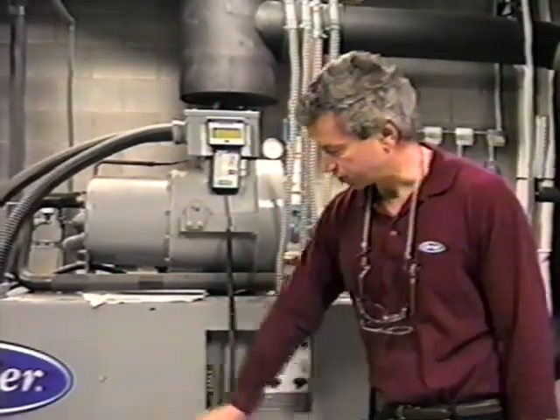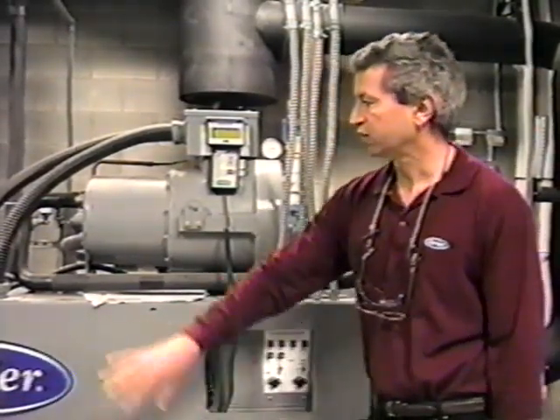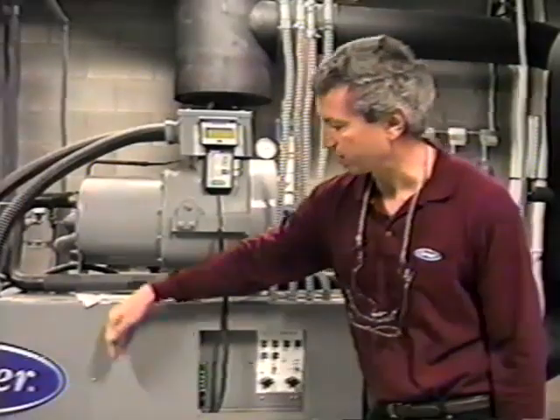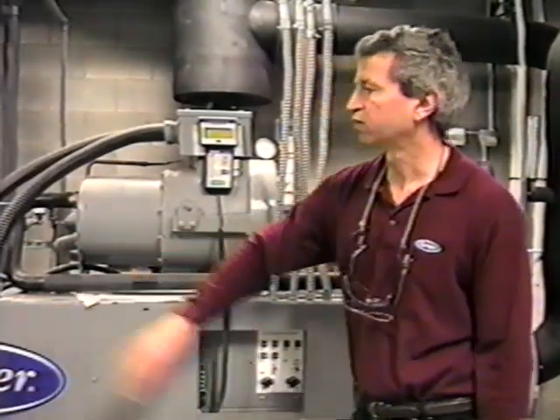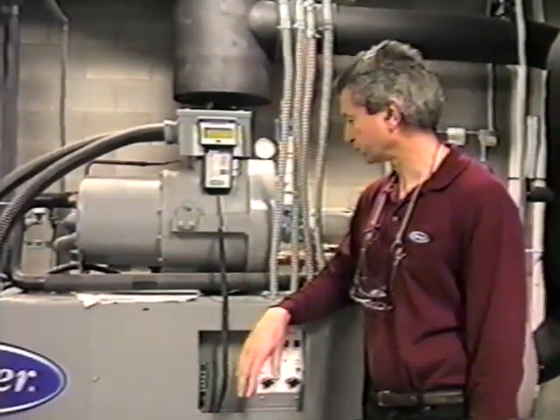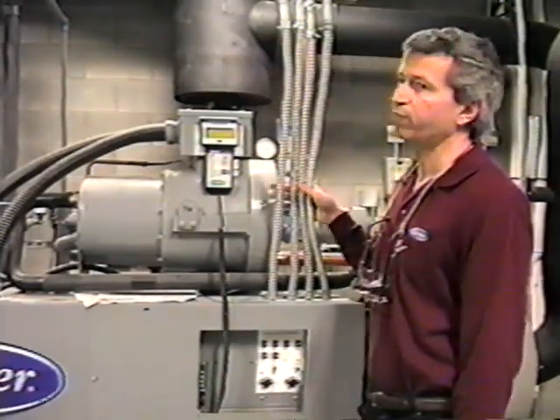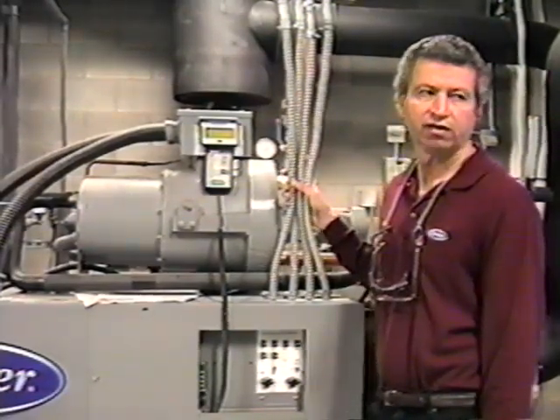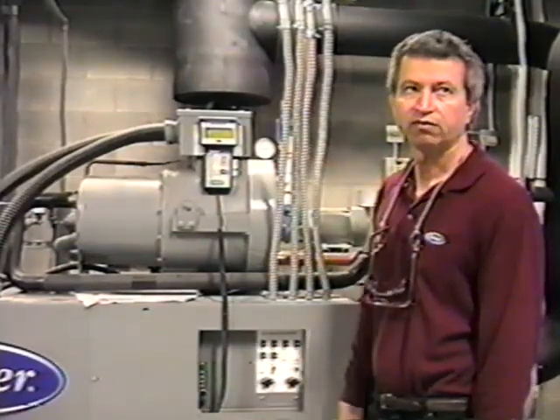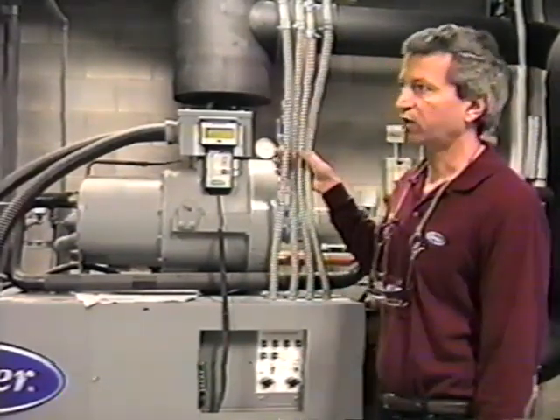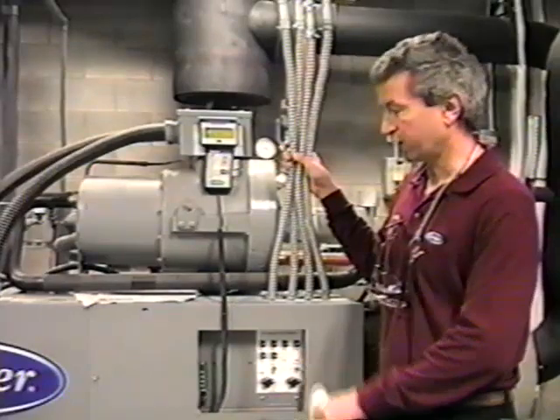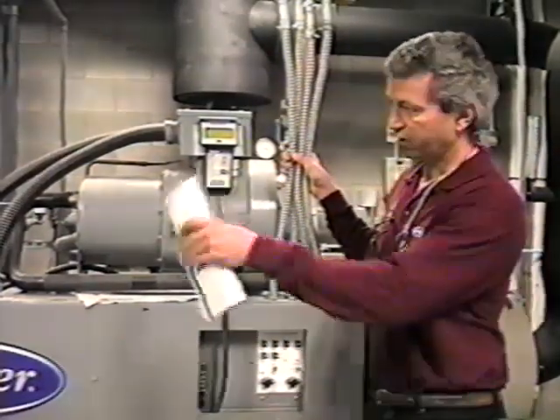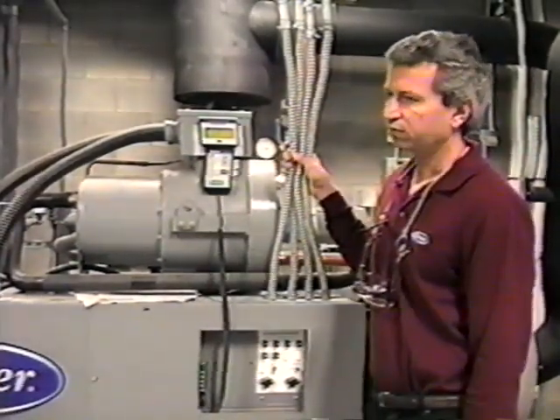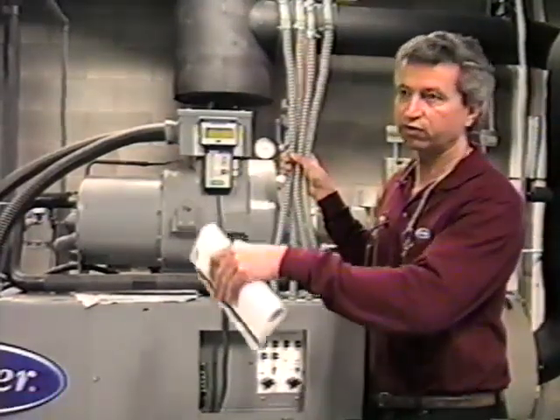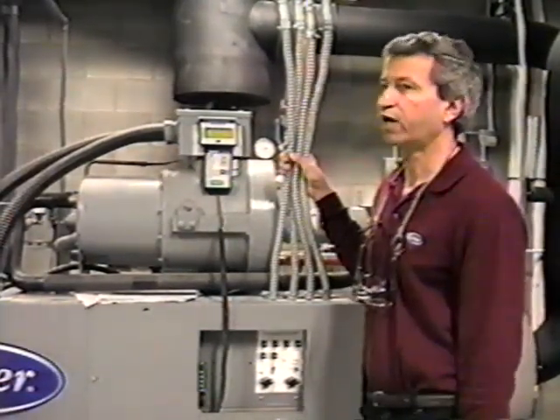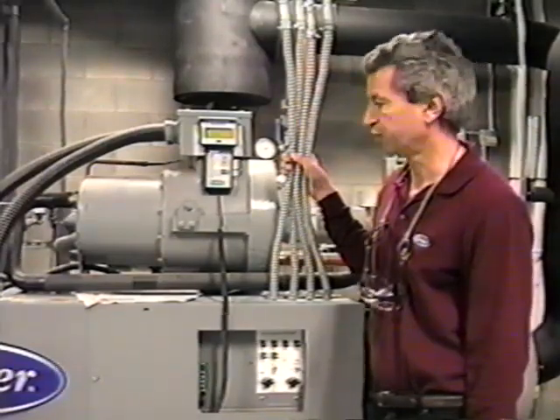And all your boards essentially are under this panel. And like I said, your high voltage portion is separated with a divider and is essentially over on that side. I believe there's a separate control source, if I'm not mistaken, probably in one of those panels over there, that provides a 115 volt source to the control side of the machine. And then you have another, I believe this is 460, another 460 source providing the high voltage power to the machine.